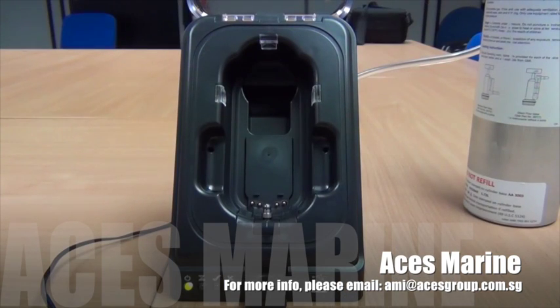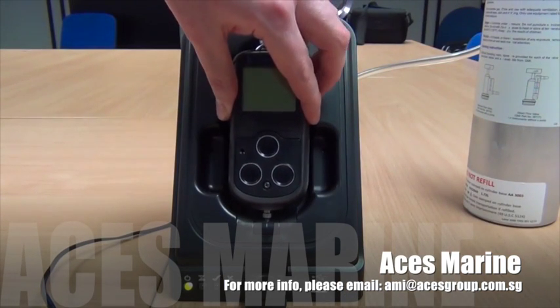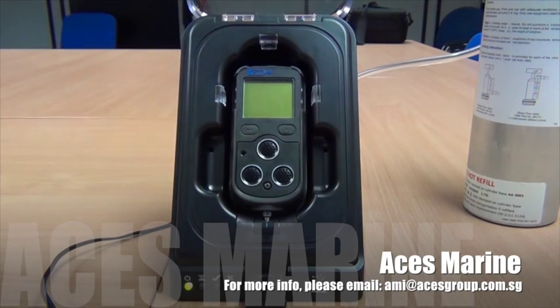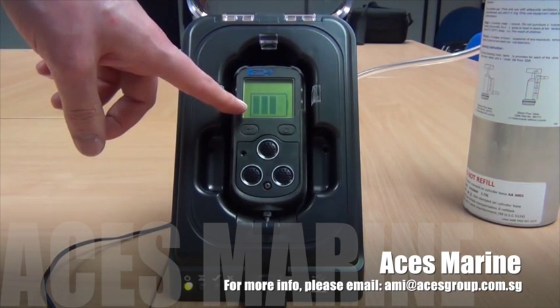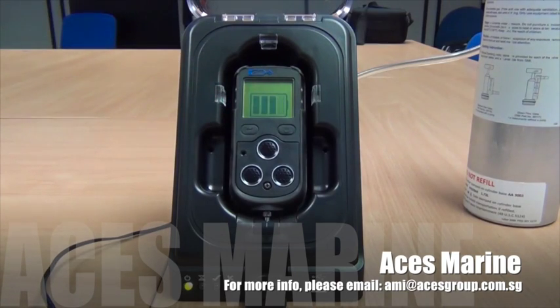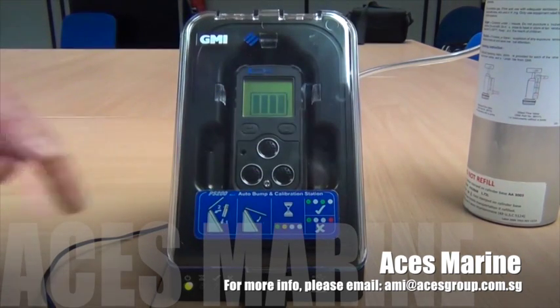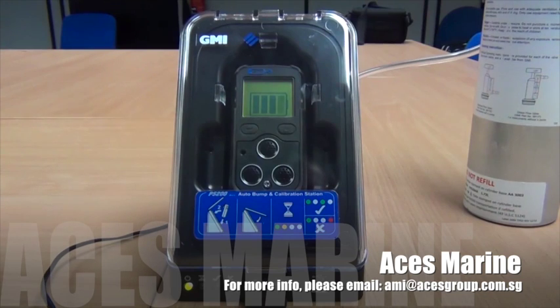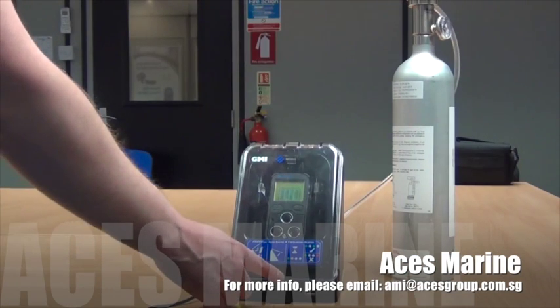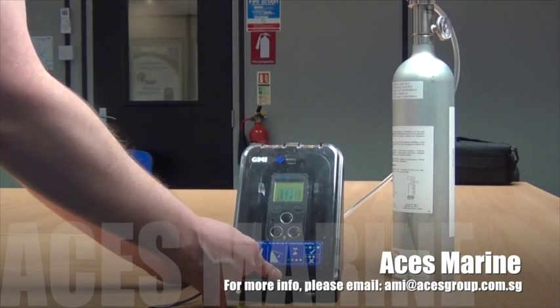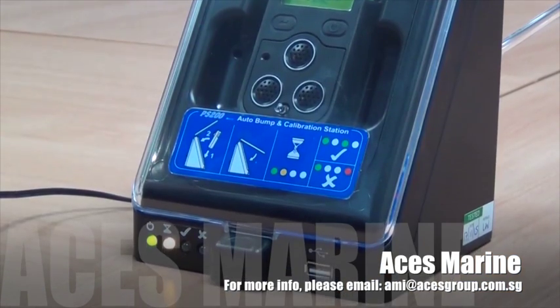With the ABC now programmed with the GMI USB, all that is done now is the PS200 instrument inserted and the door closed to start the test. Ensure the instrument shows charging on the front before we close the door. This tells us that there's communication between the instrument and the ABC. And closing the door with one finger activates the switch on the ABC and starts the test.